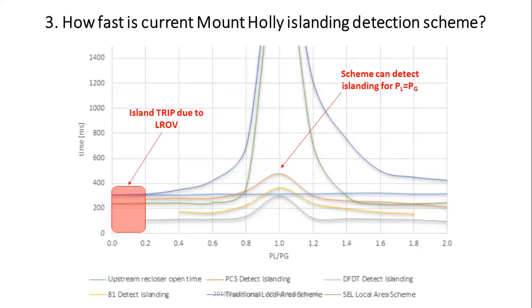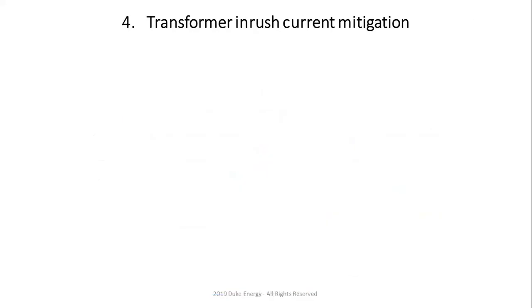Just to give you an example, settings can be 1.1 per unit. They can be like 132 and 144 volts. Voltage is measured, it was like in the 145 to about 164 range. So there's no way to get a seamless transition during PG much greater than PL. You see 0.0, 0.2. 0.2 is the smallest ratio that we managed to still seamlessly island, but anything below that we have tripped. And for PL over PG equal to 1, we have tested this probably about 15 or 20 times for PL equal to PG, and every single time we managed to do that.